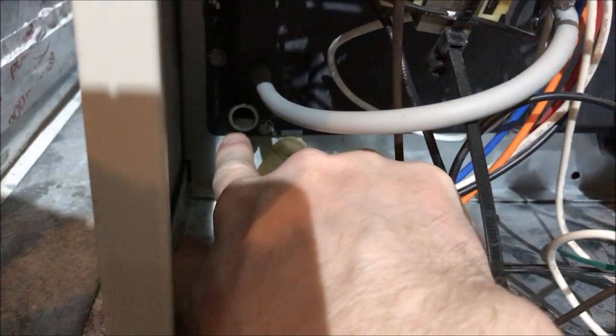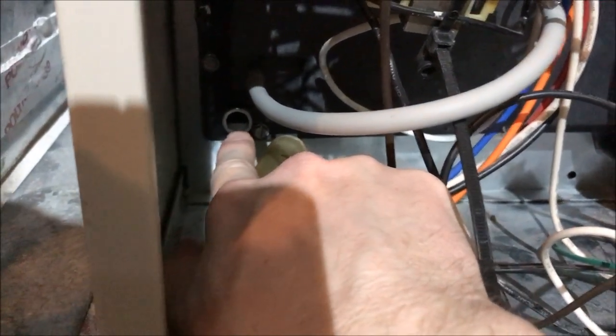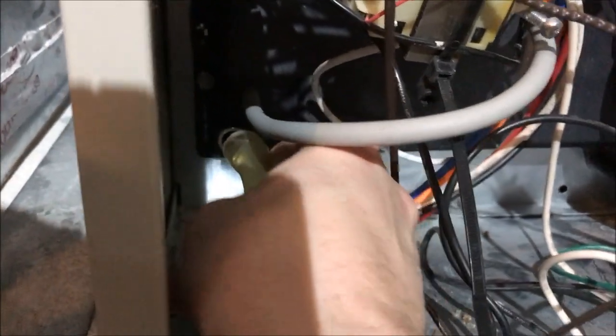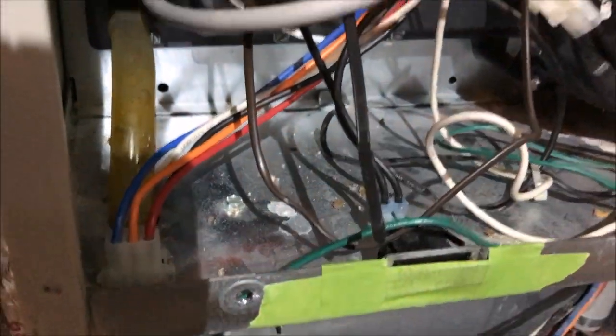A good best practice is to take your hose off here and look at this outlet hole and make sure there's nothing blocking it. In my case I had a bunch of debris back there. Just growth of some kind. You can see it's kind of, I haven't cleaned it all up yet but it was the bottom of the pan.